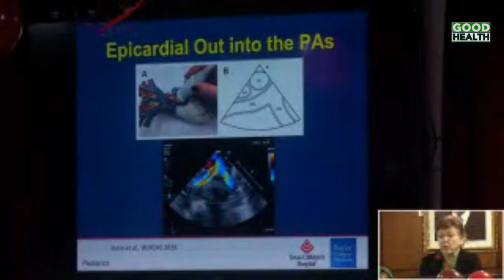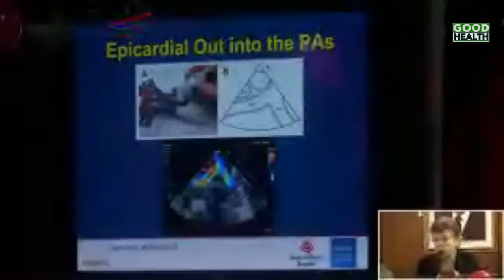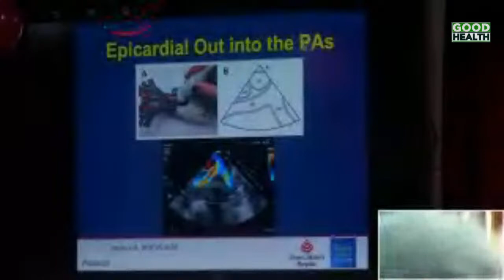Okay. The last thing that I'll talk about is just the sterilization of the probes, regardless of whether we use a TEE or an epicardial probe. It's very important that these probes be cleaned properly. We keep our epicardial probes in the operating room, so they don't need to be cleaned beforehand. But if they're being brought to the operating room to be used, they need to be cleaned before the surgery, before they're brought into the operating theater. And then at the end of the case, they need to be wiped down with an enzymatic sponge and then cleaned properly. For our TEE probes, similarly, we wipe them down with an enzymatic sponge at the end of the case, and then we Cidex them, we clean them, and then put them in a sheath so that they're not hanging out in the open in the rooms before we go back to the operating room. We also test our TEE probes to make sure that there are no electrical leaks, that there are no cracks in the probes or problems that can cause severe damage in the patient.